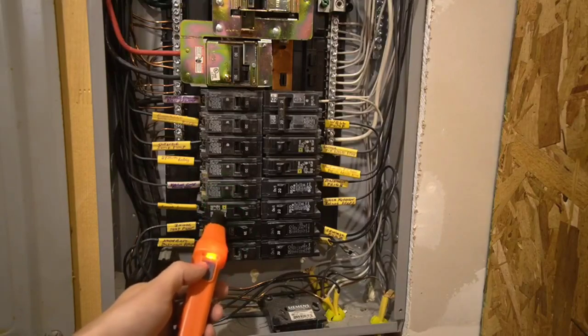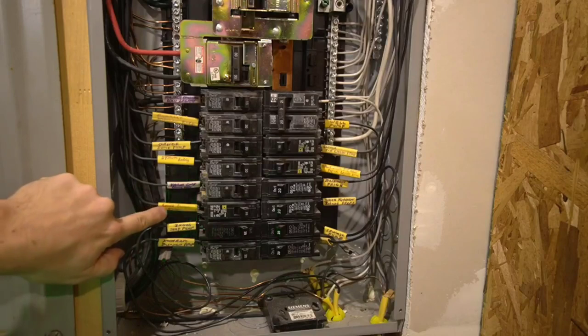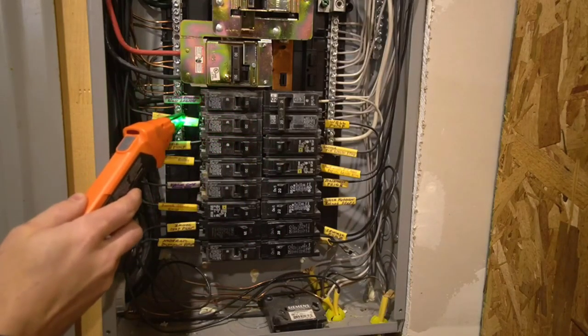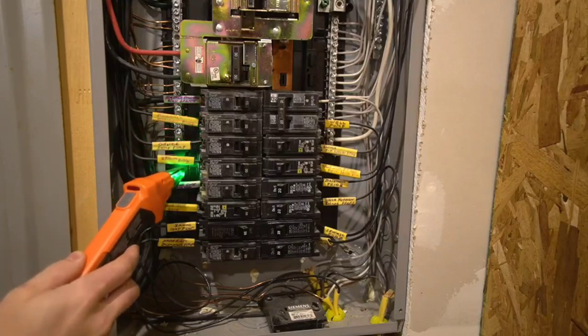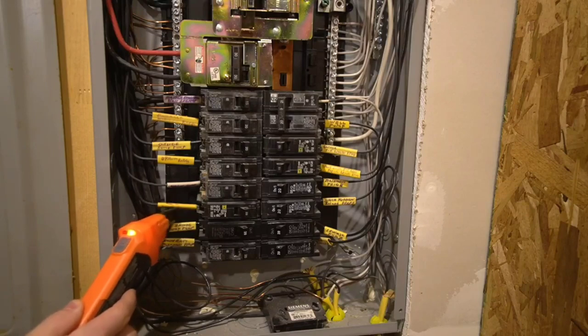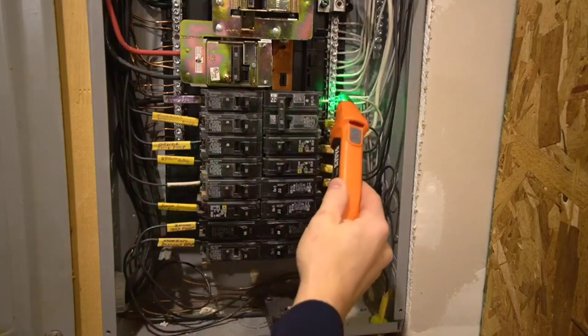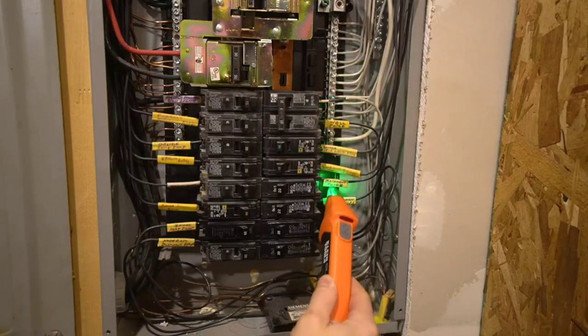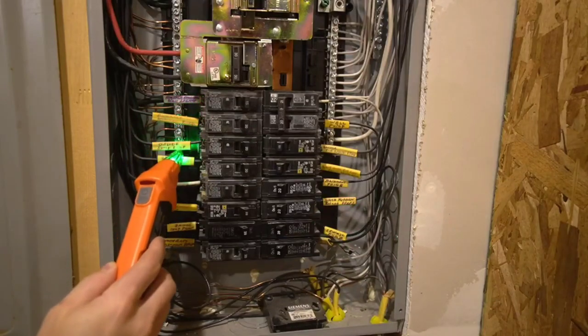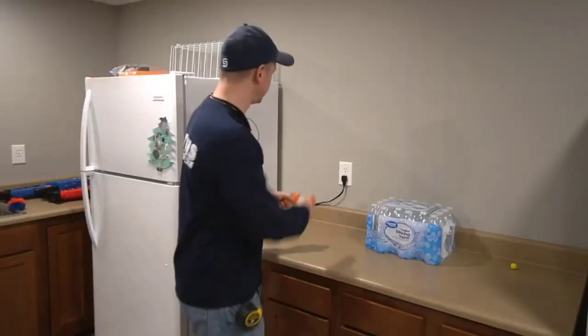Right here — that's telling me that that is the one, and sure enough I've got it labeled here: south garage receptacles. So that is the correct one. It also reads really well if you go over the bare wires. You can see south receptacles again. See, it's not picking anything up on the others, then whenever I come back across here — right there it is.